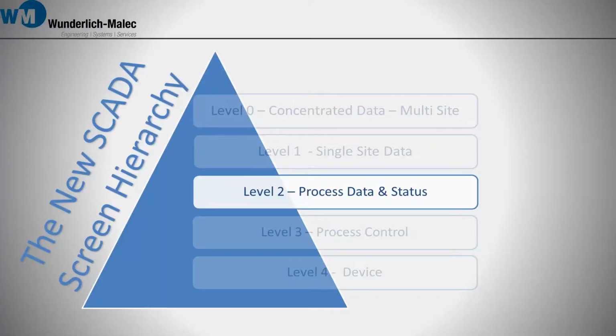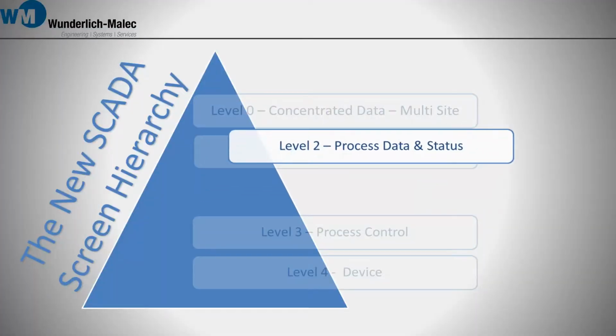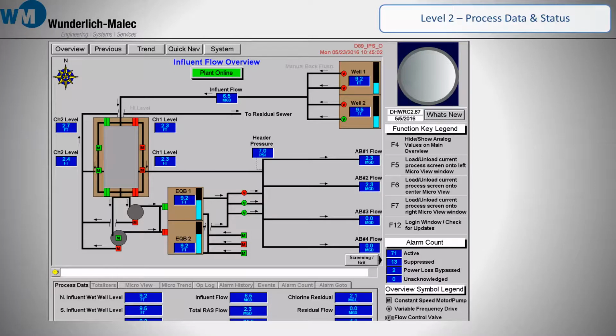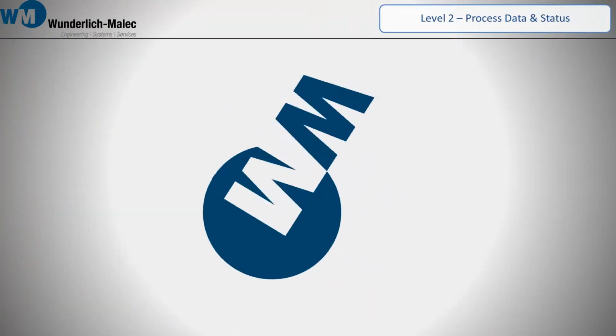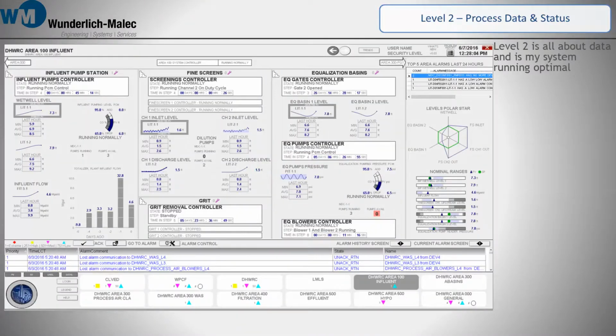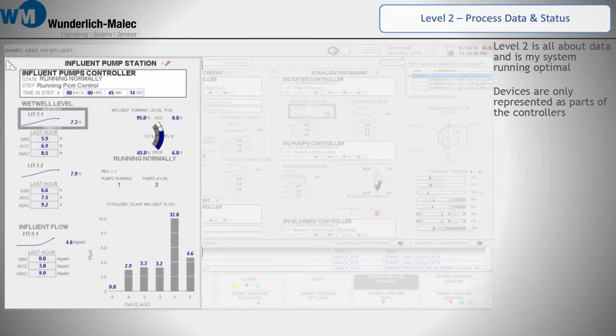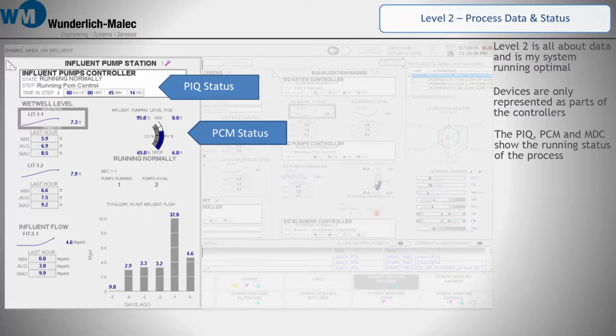Level 2 excels at showing process data and status. At the present Level 2 screen, we again see a great layout of the area and the operation of some of the equipment, but nothing to help the operator understand how the system has been running. Situational awareness is all about data and is my system running optimal. Devices are only represented as parts of the controller. The PIQ, the Process Control Module, PCM, and pump set statuses all clearly display how the process is running.